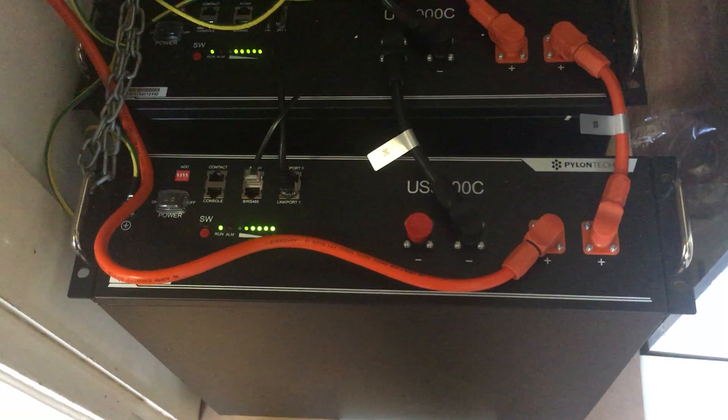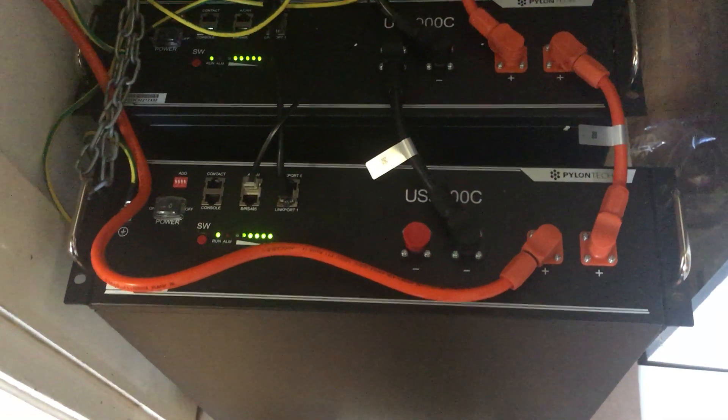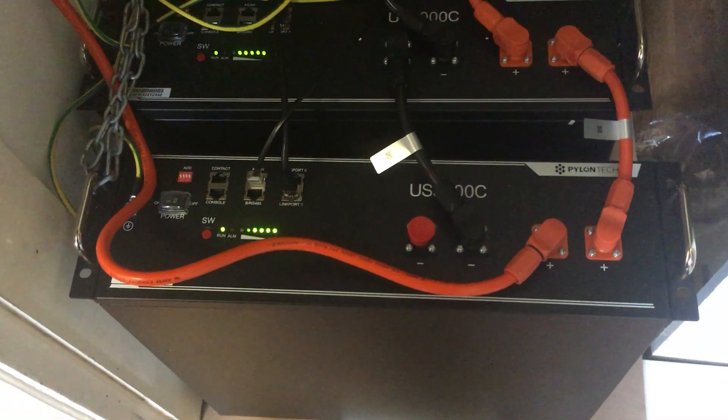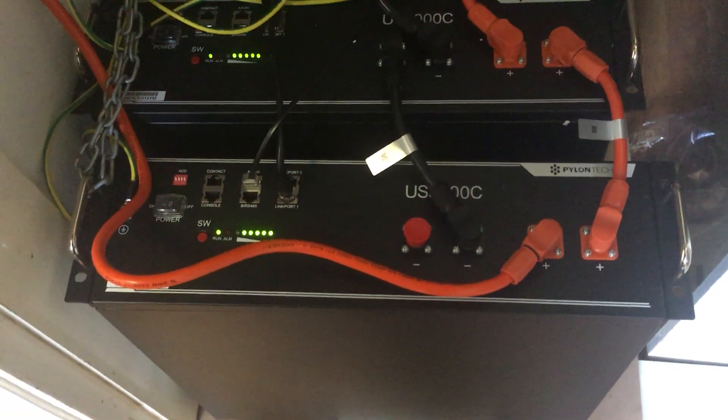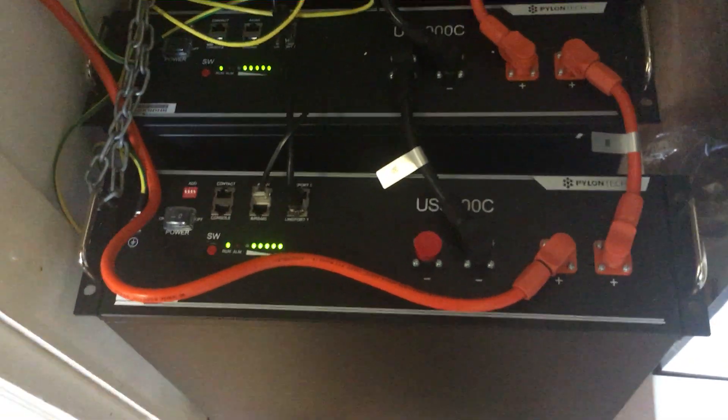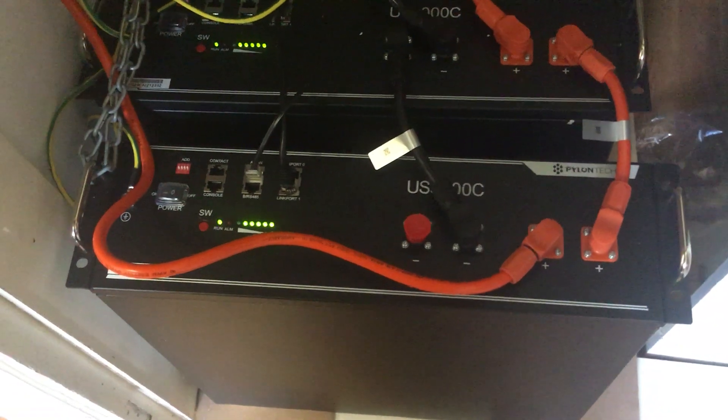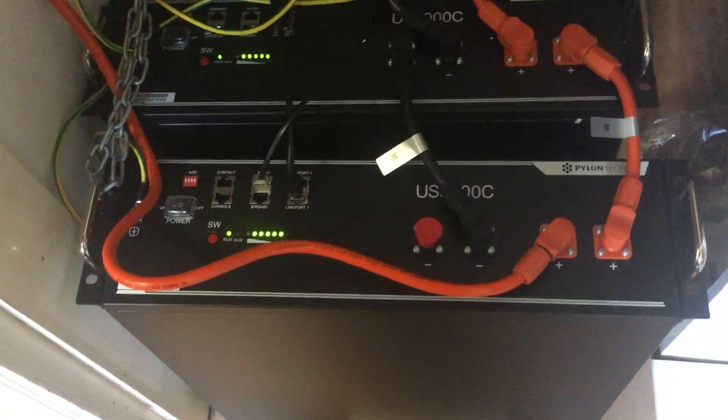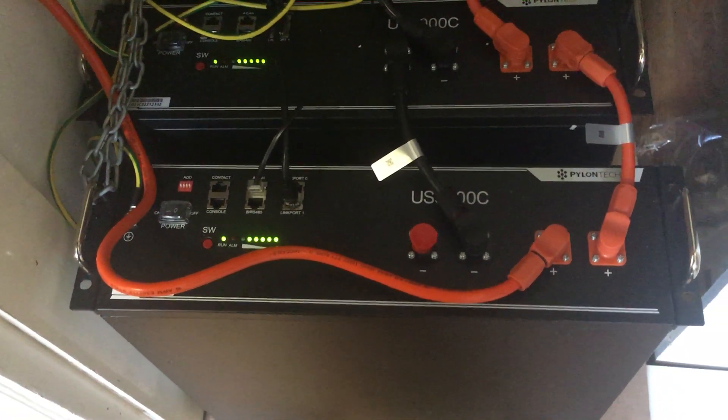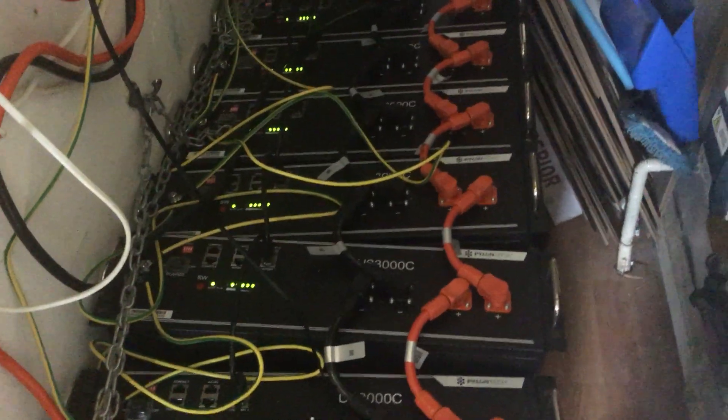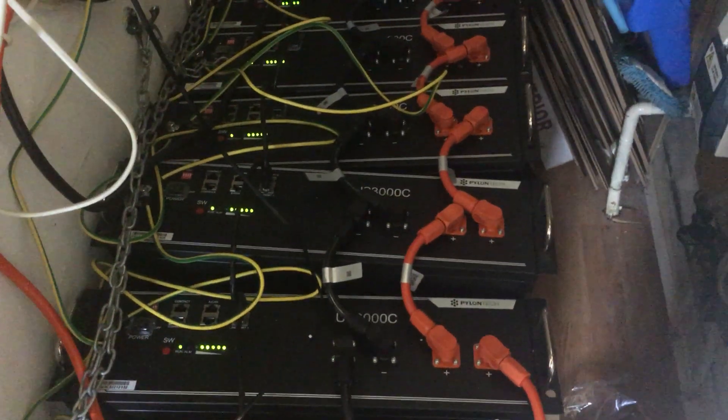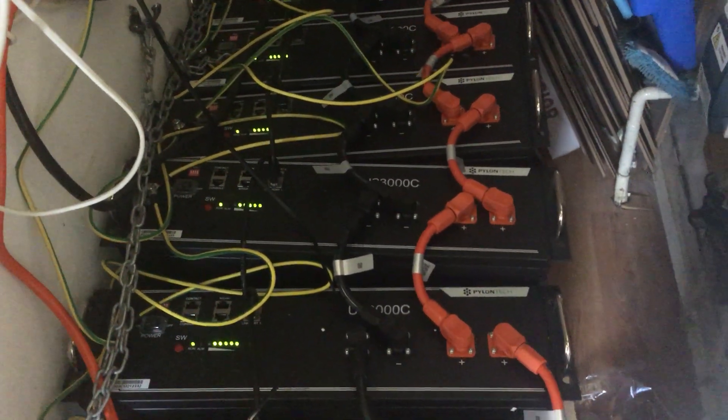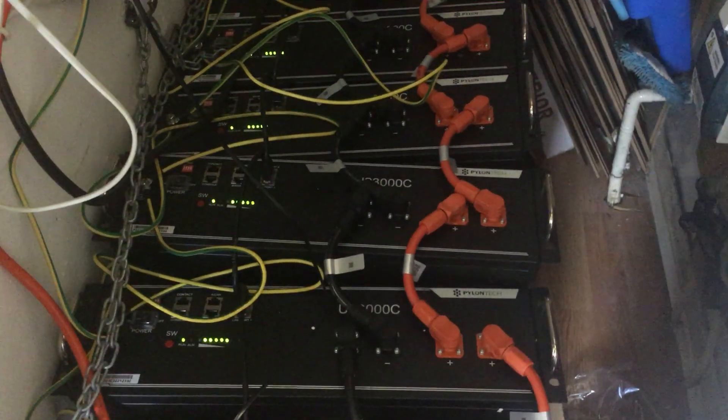And what that does is basically tell the battery BMS system to check the network connections of each battery. So once you do that, what you'll see if you watch my other videos is all the lights will light up on each battery in turn. So the first five will light up, the second one, the third one, the fourth one and fifth one, six and seven. They'll all flash all together in the end. That means you've got a successful BMS connection between the batteries. The batteries are all talking to each other, they're working all fine.